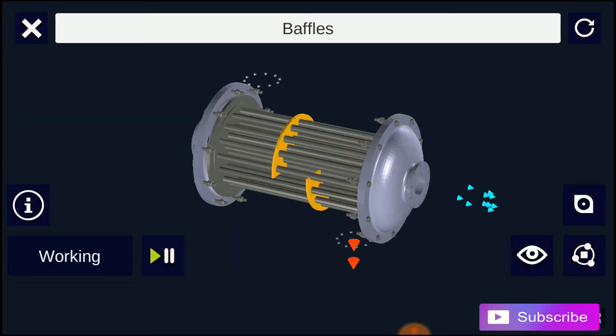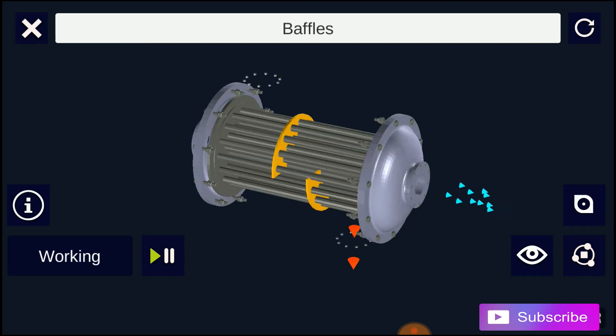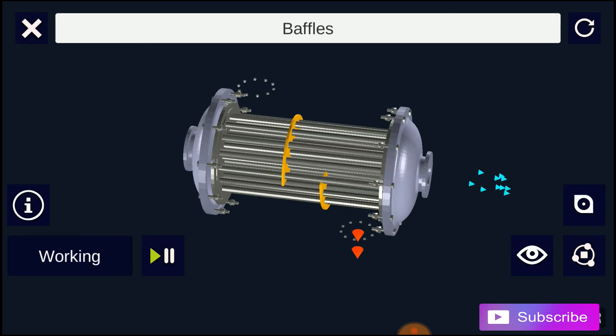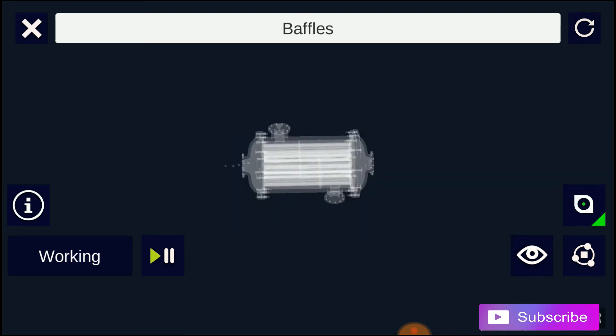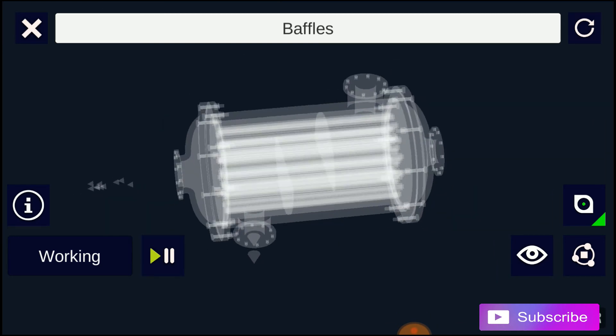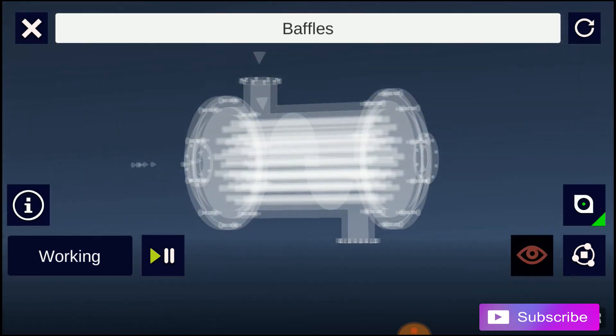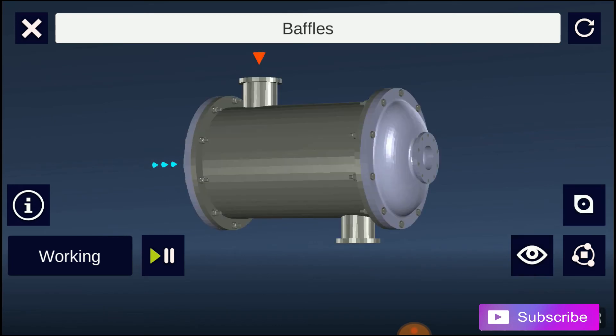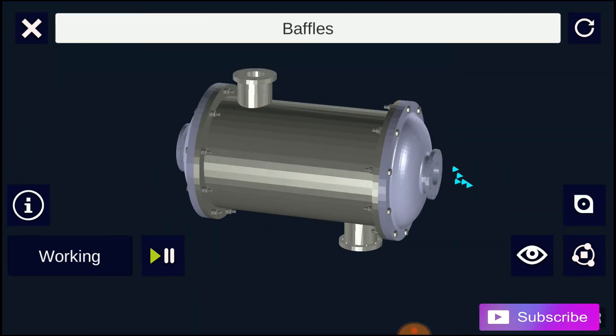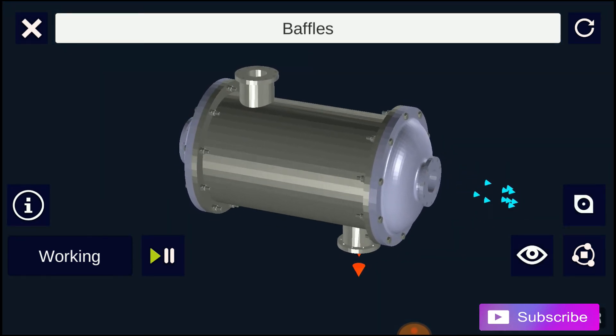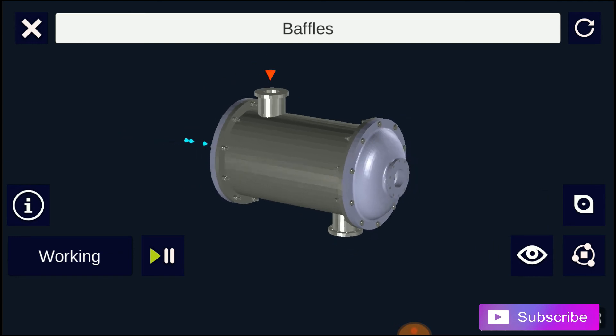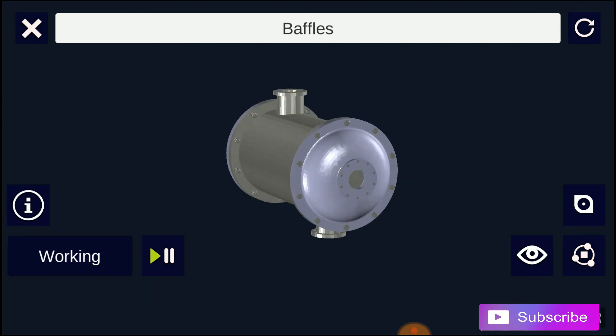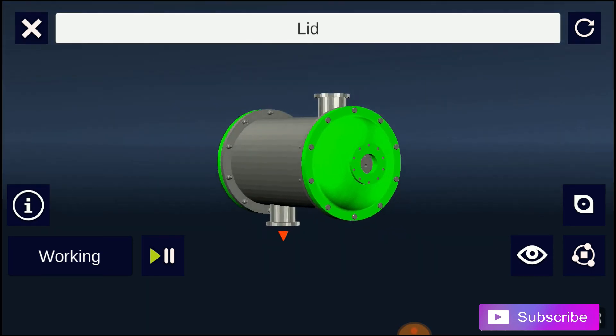Counter-current heat exchangers are most efficient because they allow the highest log mean temperature difference between the hot and cold streams. Many companies however do not use two-pass heat exchangers with a U-tube because they can break easily, in addition to being more expensive to build. Often multiple heat exchangers can be used to simulate the counter-current flow of a single large heat exchanger.